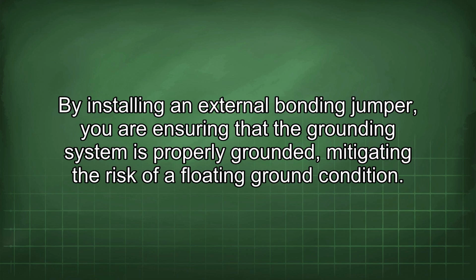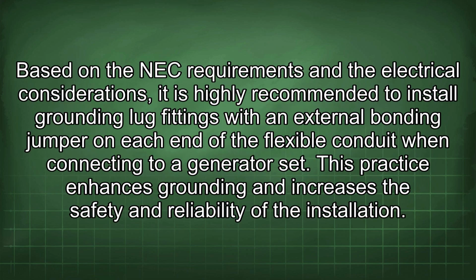a floating ground condition. Based on the NEC requirements and the electrical considerations, it is highly recommended to install grounding lug fittings with an external bonding jumper on each end of the flexible conduit when connecting to a generator set. This practice enhances grounding and increases the safety and reliability of the installation.